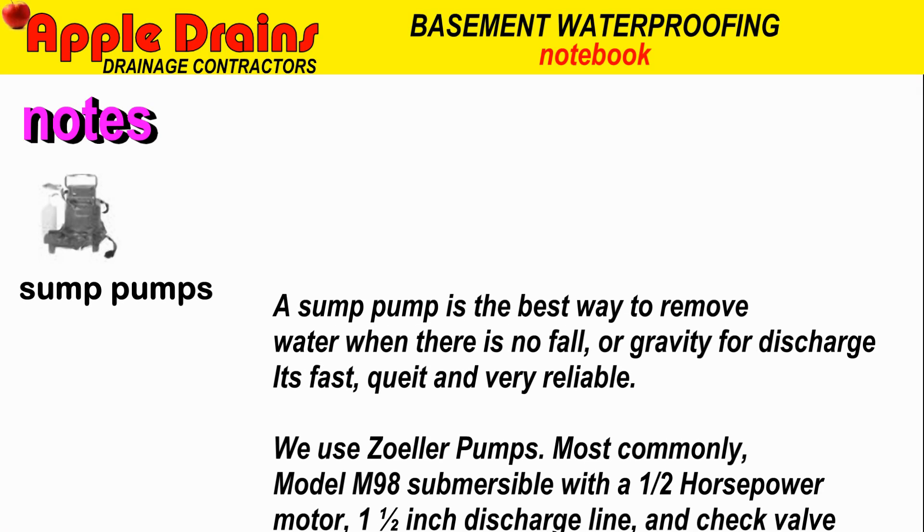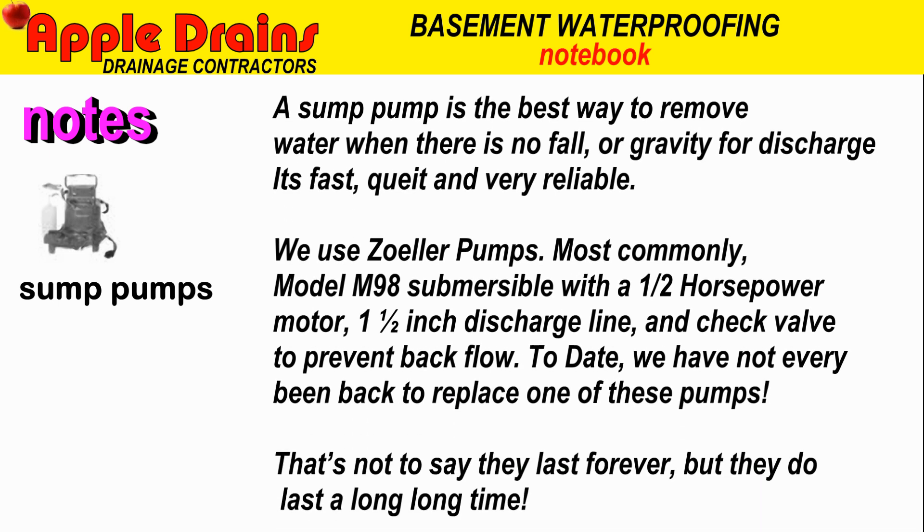The sump pump is best used to remove water when there's no fall or gravity for discharge. It's fast, quiet, and very reliable. We use the Zoeller pumps, most commonly model M98 submersible with a half-horsepower motor. It has an inch-and-a-half discharge line and a check valve to prevent backflow. To date, we have never been back to replace one of these pumps. That's not to say they last forever, but they do last a long time.